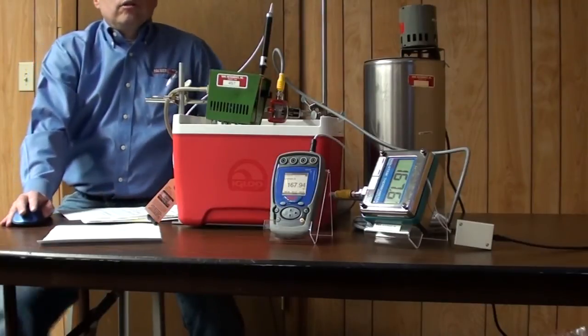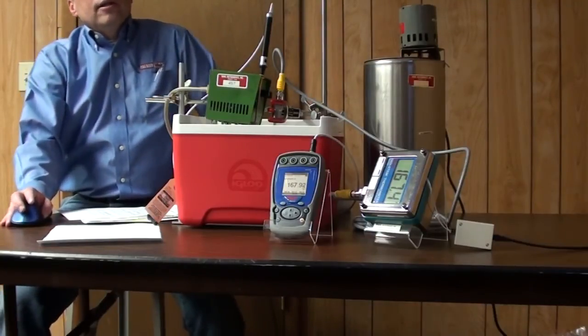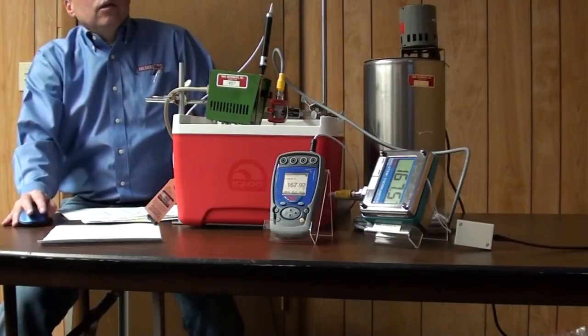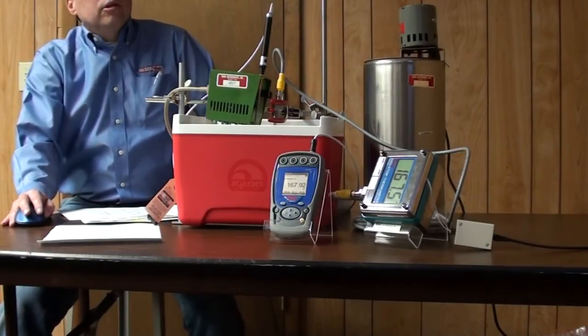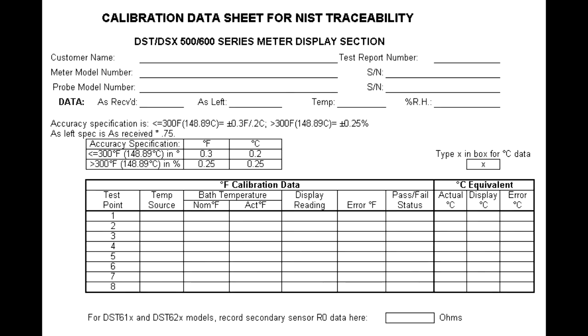The next section of that slideshow is to go over the test report. And again, we kind of went over this. You might be able to see it a little better. All the information: model number, serial number, manufacturer's instrument number. If you give your instruments instrument numbers, the data before and after. If I'm calibrating this unit and we just bring it in, we're going to take the before adjustment data. This is the ambient temperature and relative humidity. We would record that. And then here's our calibration data. We'd put what the source is.